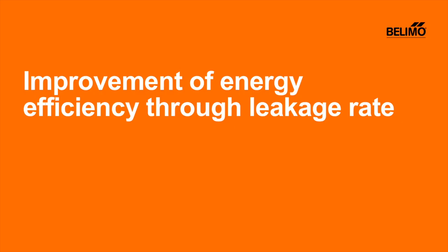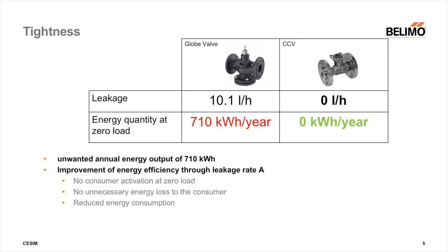Improvement of energy efficiency through a better leakage rate. If a valve leaks when closed, energy is transported from the generator to the heat exchanger. This amount of energy is delivered to the heat exchanger, and it can be assumed that this energy output is not required if there is no flow or power requirement from the valve. This amount of energy, therefore, can be regarded as a loss.